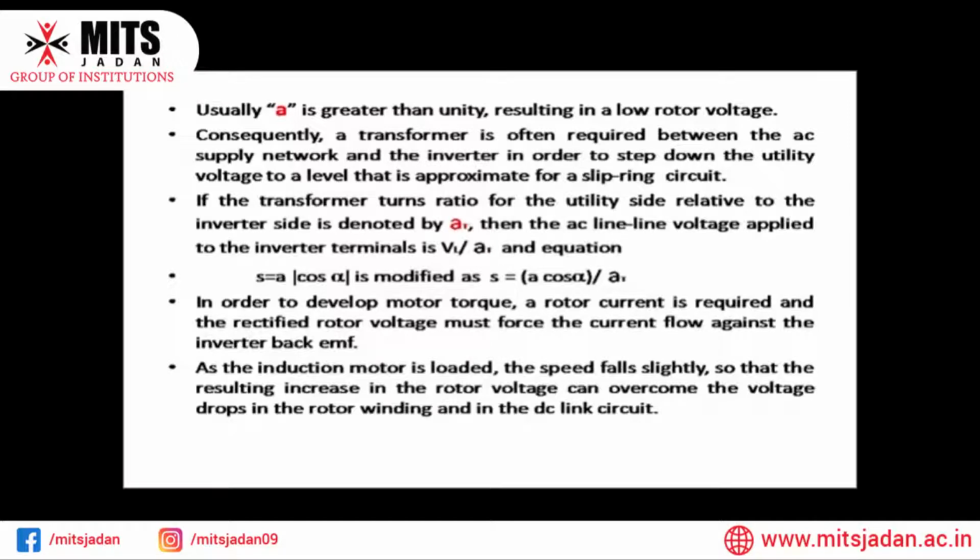Further, usually the value of A is greater than unity, which results in low rotor voltage. Consequently, a transformer is often required between the AC supply network and the inverter in order to step down the utility voltage to a level that is appropriate for a slip ring circuit.